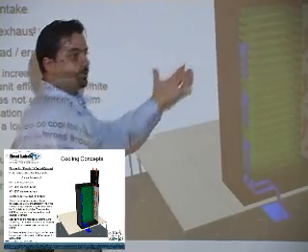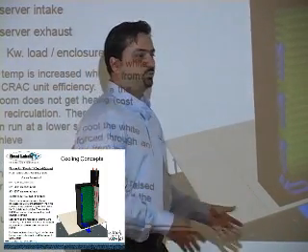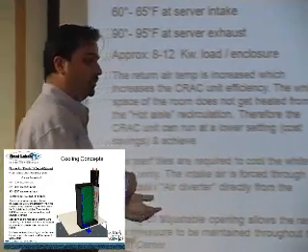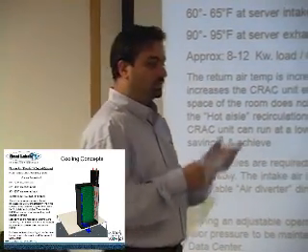And the fans on the server actually have to create that negative pressure to pull through on all their traditional hot aisle, cold aisle concepts. What we're doing now is ducting by very simple methods. No fans, it's just using the pressure of the raised floor, ducted right to the front space between the air intake and the servers. And behind the mesh door, we're seeing some people use clear plexiglass with just a perimeter vented, just a little assist as well, to do some mixing of that.